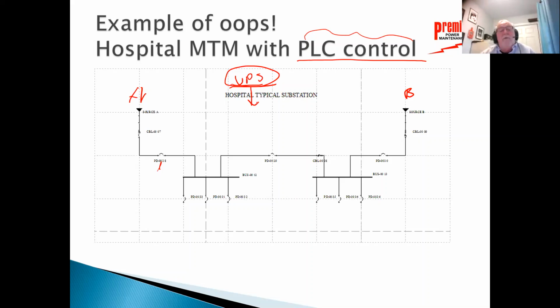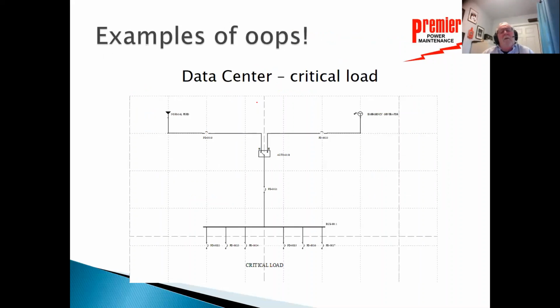So sure enough, about 5 years after it was placed into service, the UPS started dying, voltage started declining. The PLC noticed the voltage drop and decided to trip all the breakers so that it would make sure that they could operate before the voltage was gone. That certainly wasn't what the hospital desired. It looked like a steel project that nothing could go wrong on, but that single point of failure was there. There's another system I went and looked at and was called out on in the middle of the night.